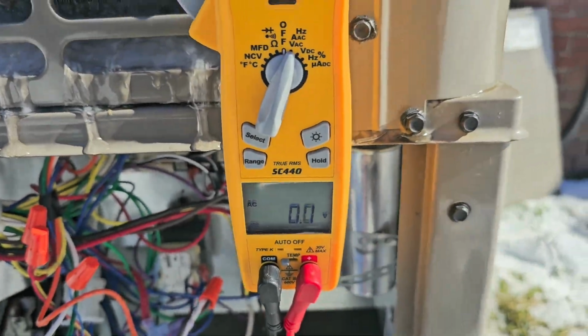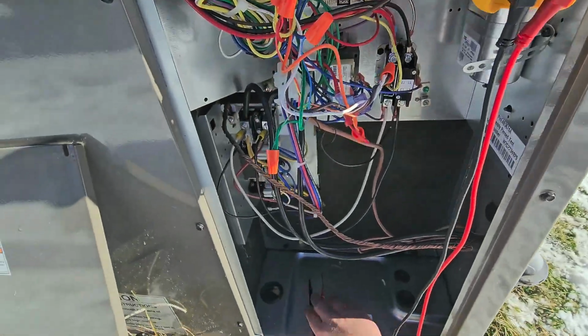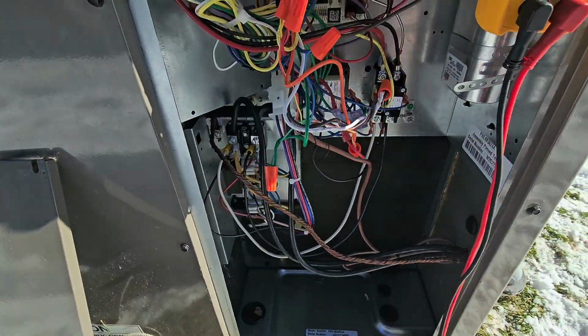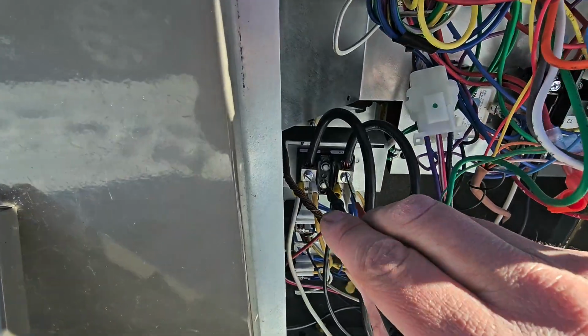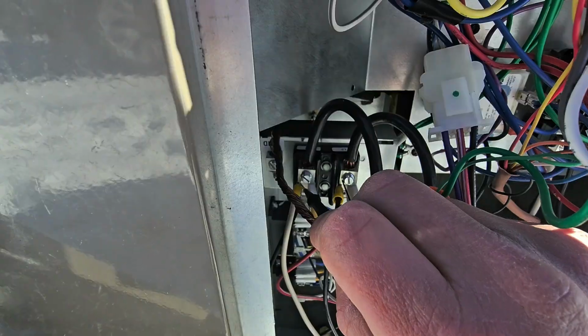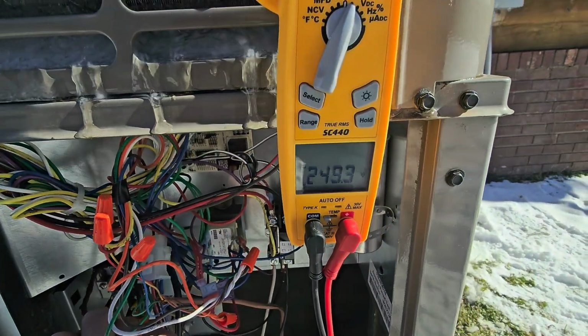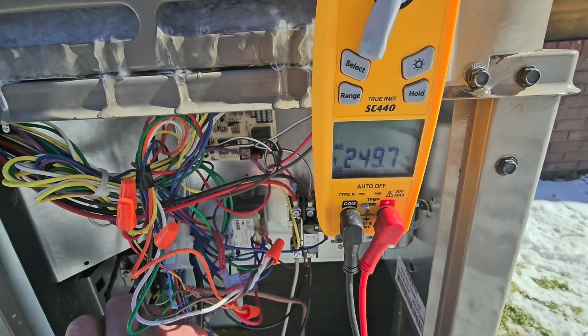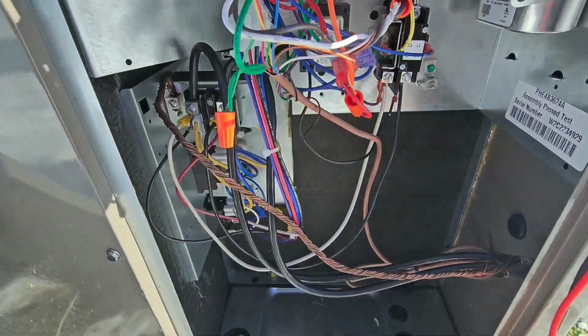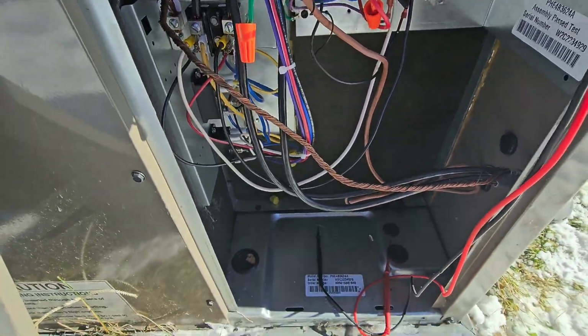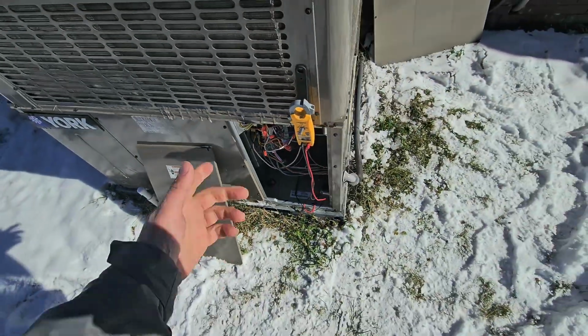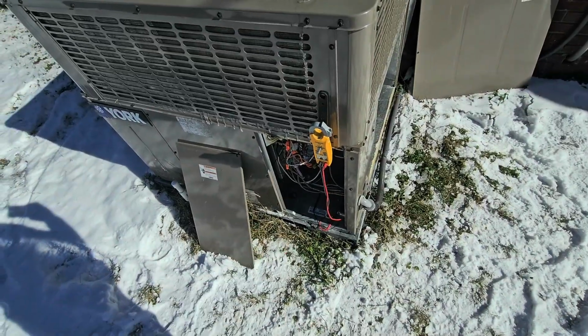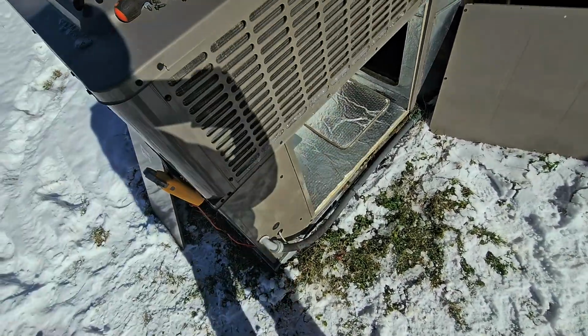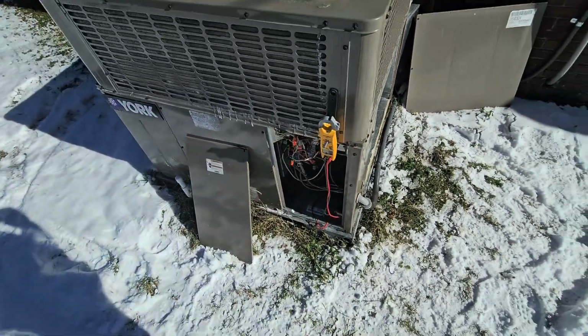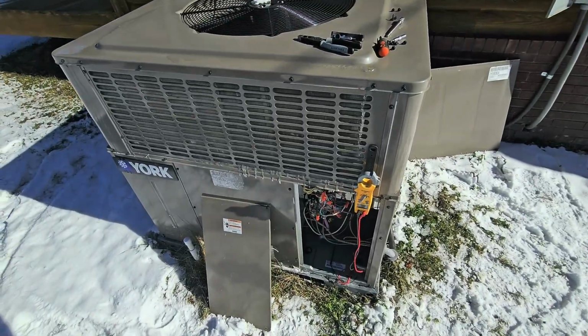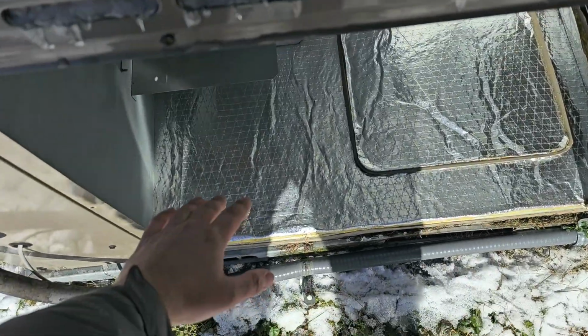Meter on volts AC. Take my meter leads and just verify, hey, we got 249 volts. So there's plenty of voltage. Everything's wired up. We got a new heater kit. We'll wait until the thermostat calls for emergency heat, and then I'll show you them glowing, and then I'll show you the supply air temperature. Motor just kicked on. I can feel the heat.